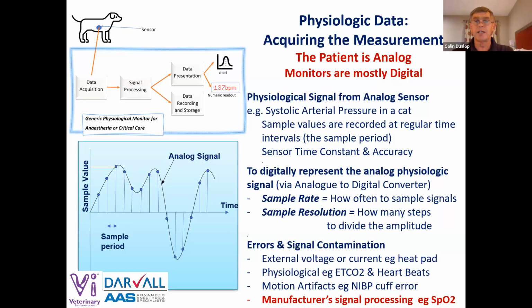Some sensors are digital, some sensors are still analog, but the analog signal gets processed to a digital signal that is manipulated by the software of the monitor, and we have no idea what it is because it's proprietary. So a good example are pulse oximeters. There is no pulse oximeter on the market today that is not altering, massaging the pulse oximeter value to get a stable reading without using software to adjust that signal.